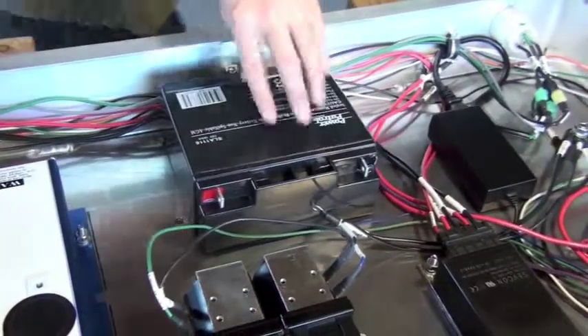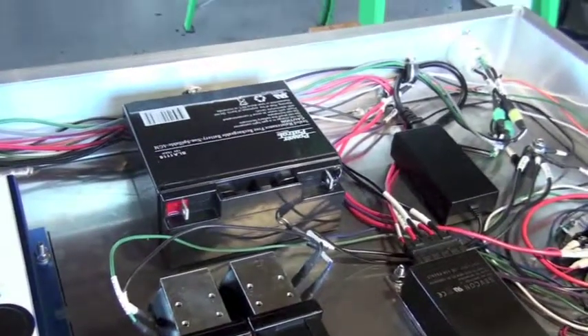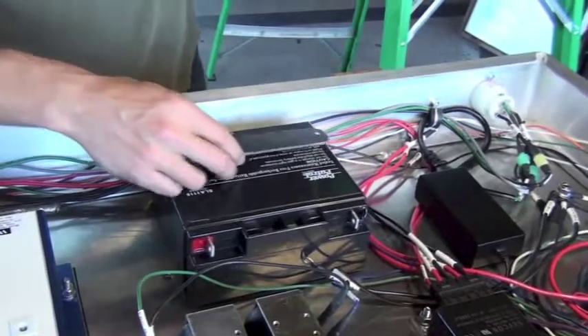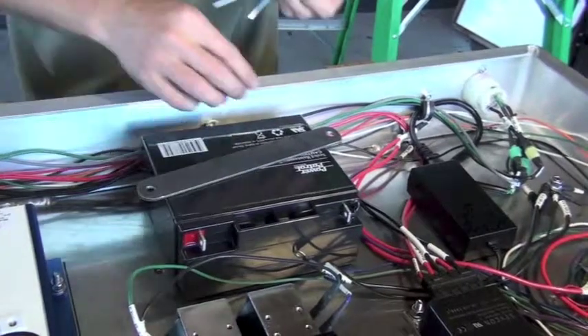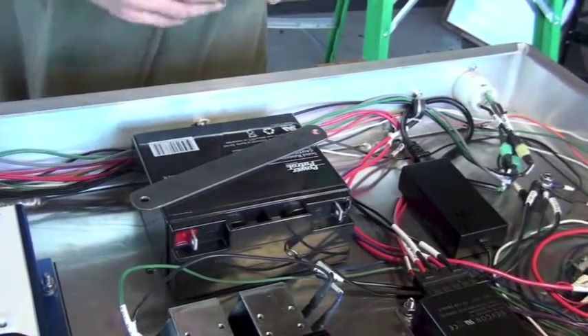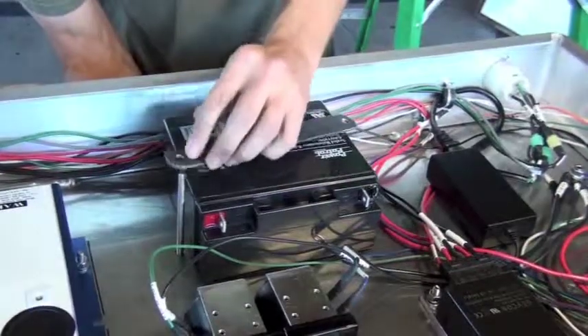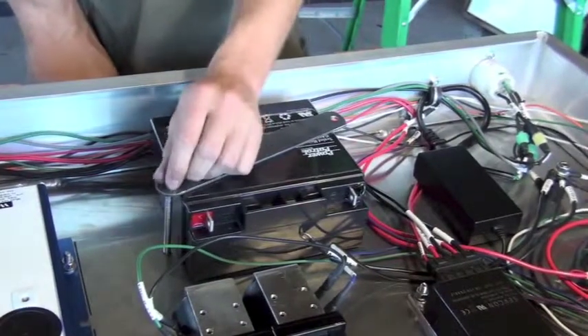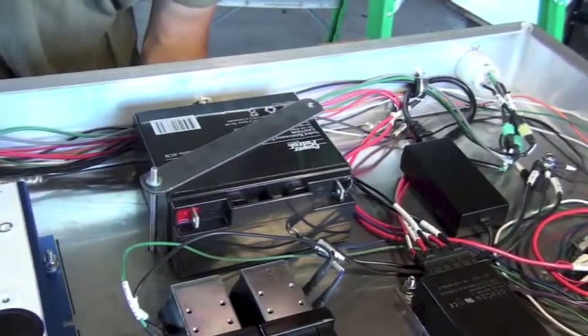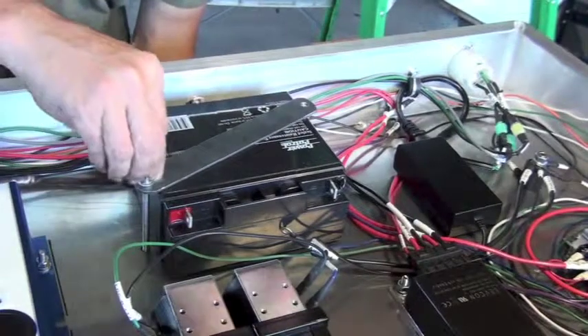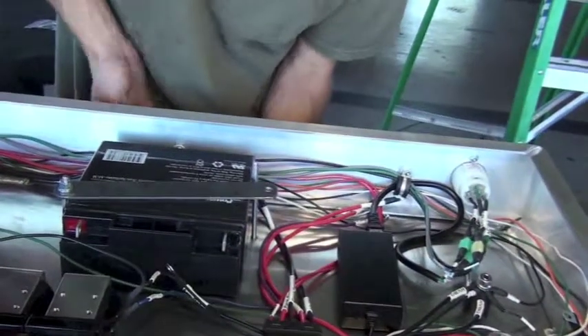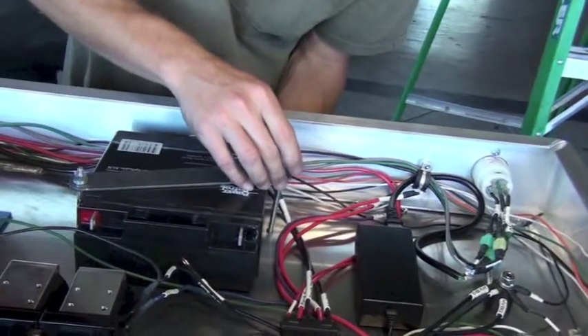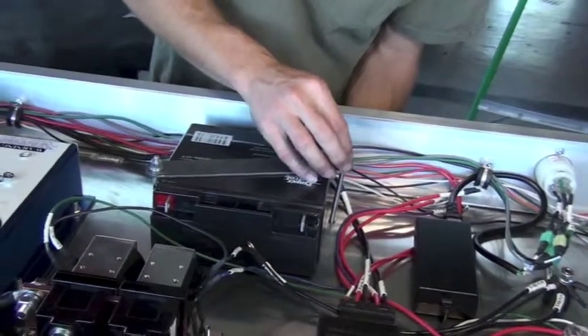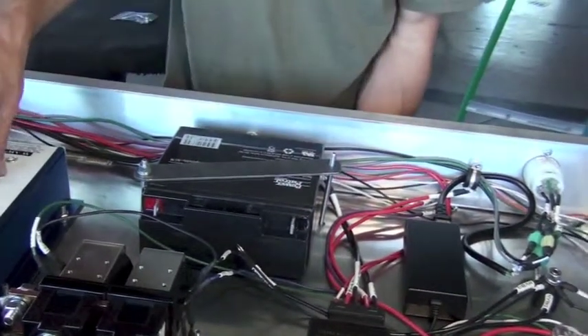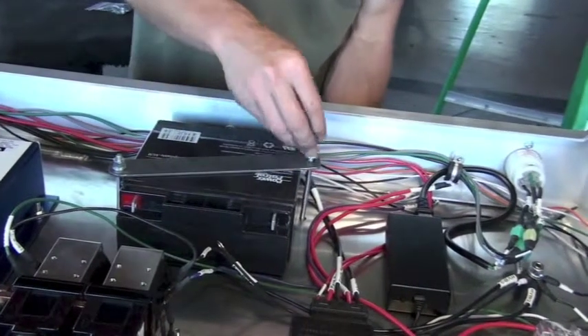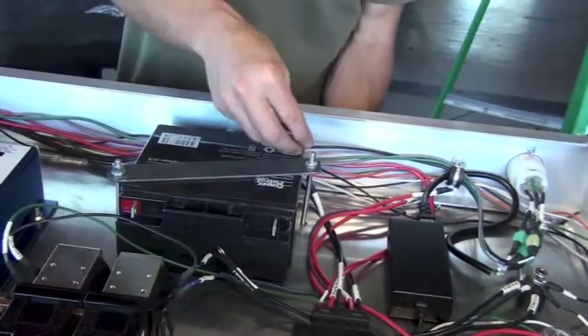And we have our mounting hardware here. One solid bar goes across the front of the battery and is mounted to the box with 2 bolts, one on either side. You may have to lift up the box a little bit more than normal to get these longer bolts inserted into the bottom of the enclosure. And don't tighten them down one at a time. Tighten each one a little bit at a time so that they tighten evenly and you have a good secure connection with the battery.